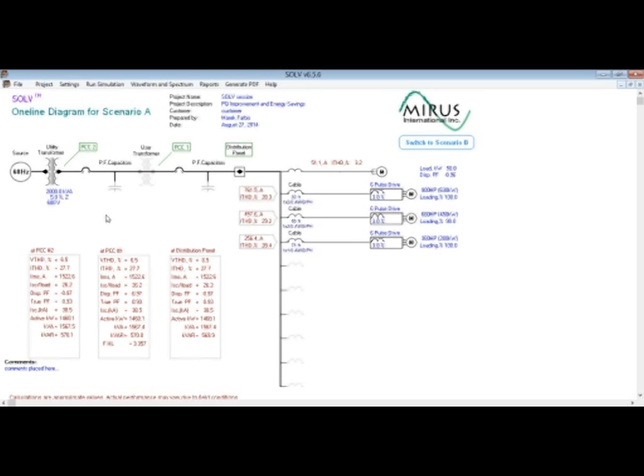Okay, a few more questions. If we had a large number of drives, can we approximate these by summing up the kilowatt ratings into one larger drive? For example, if we had 20 50-kilowatt drives, can we present them in a single line as a 1000 kilowatt drive? What inaccuracies will result? Mathematically, this is correct. You can multiply 20 by 50 and simulate this by a 1000 kilowatt drive. And we verified this in real life, that the simulation result in SOLV will be very accurate, provided that cable impedances and any power factor correction capacitors used are also provided in the simulation as real numbers.